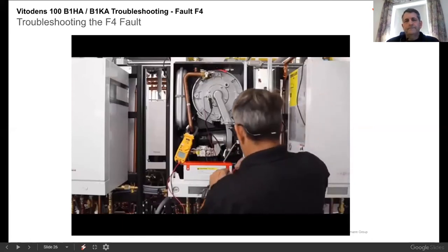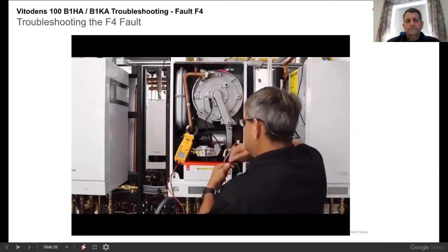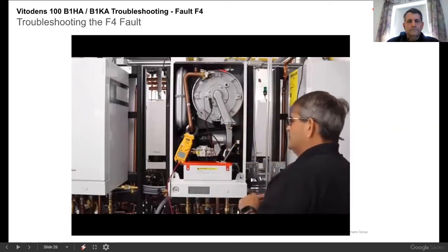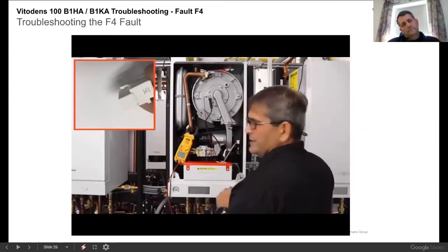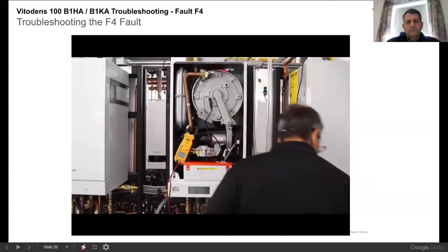And we'll check our voltage going to the gas valve. Normally what I see here with no resistance is about 106, 108 VDC. When it's connected to the burner, you're gonna get that 106, 108, because you're gonna have some resistance through the coil as well.